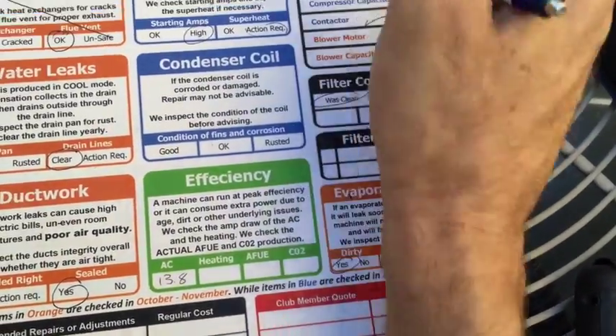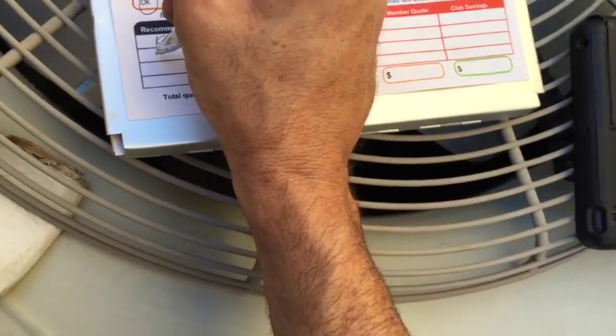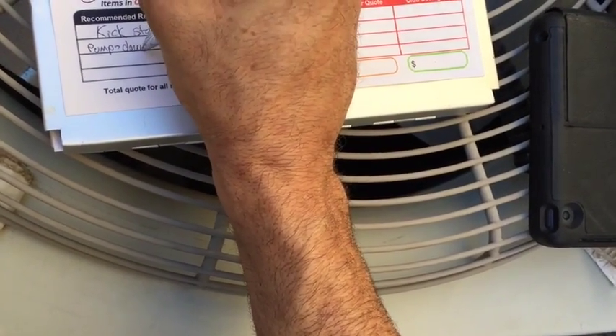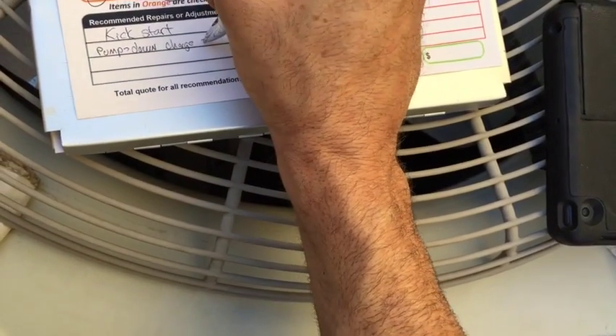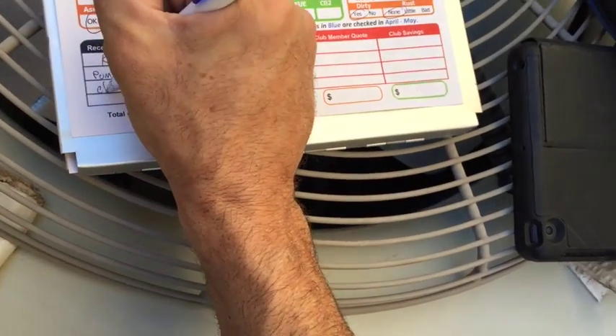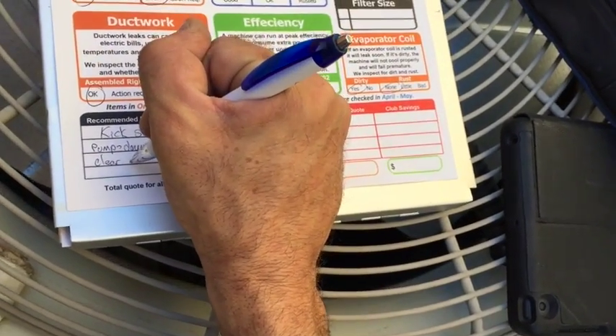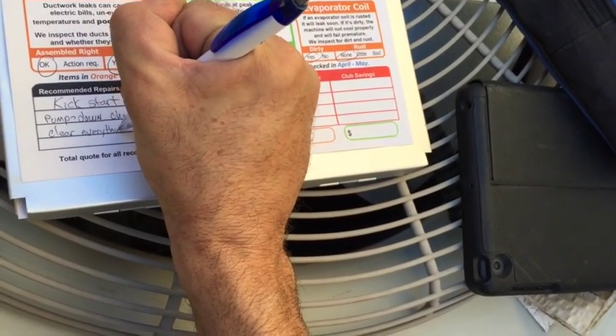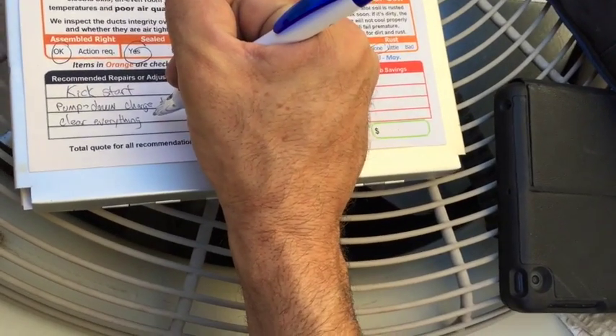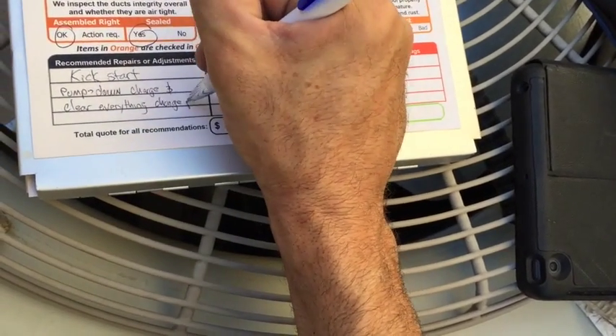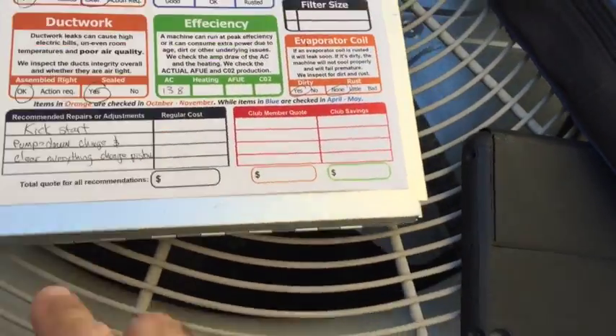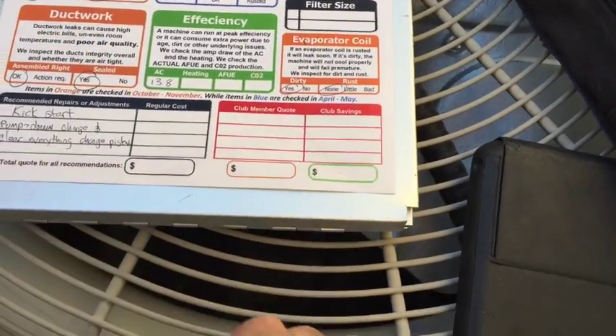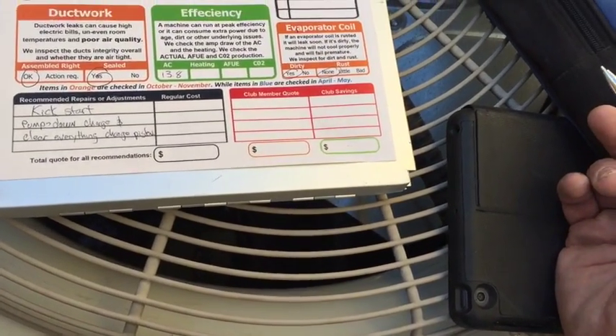So, action required on that charge. The charge is not perfect. If this thing was to last, I would want to pump down the charge and clear everything. And while it's open, we would change the piston. I don't know what's in there, but we'd get rid of it and put it in the right size. And this condenser coil's in pretty good shape too.